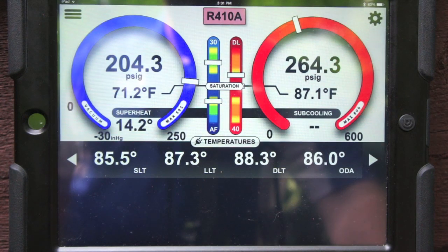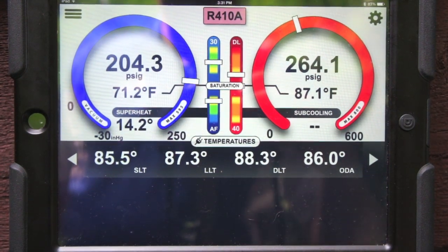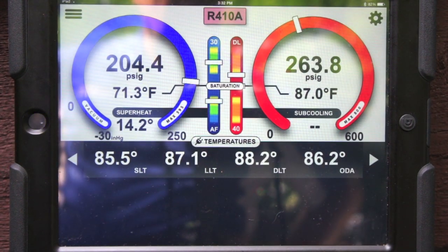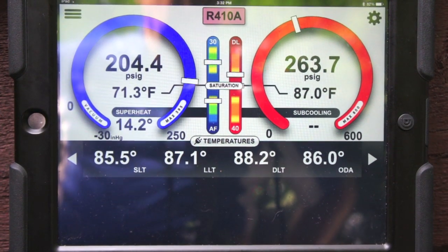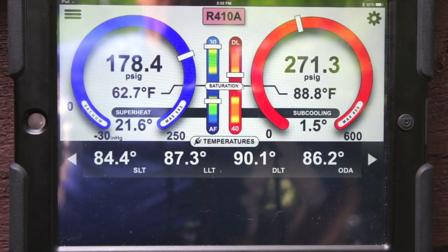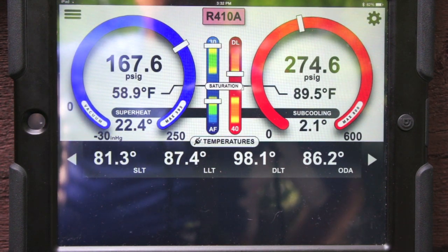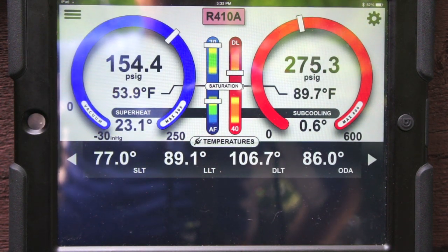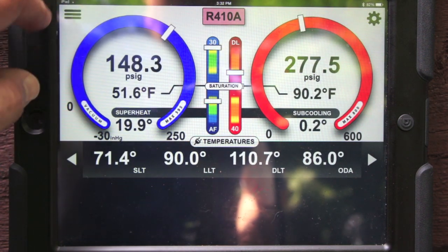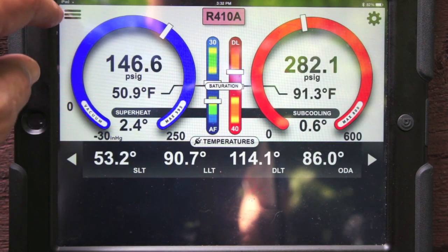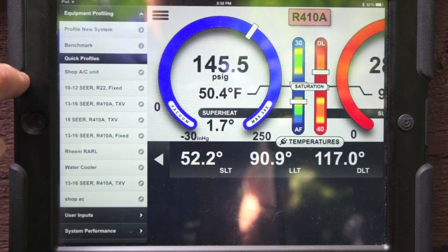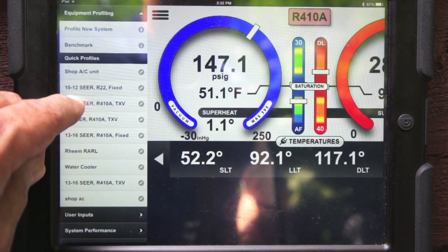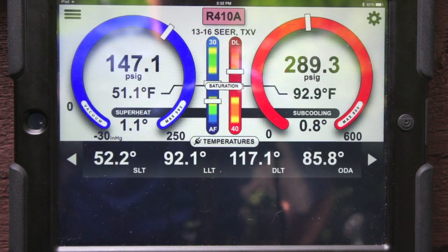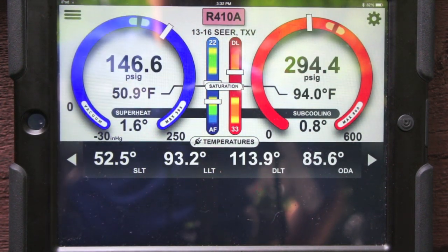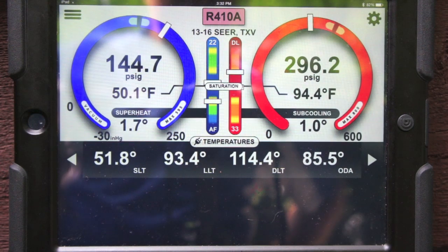We'll go to iManifold here, and we're going to go ahead and start the system up and start getting some readings. Alright, we are started up now, and you're going to start seeing some of the readings come in. So while this thing is running, I'm going to go ahead and profile the system. And this is a 13 to 16 SEER 410A TXV system. So I'm going to go ahead and select that. And that's going to put some indicators up on there showing where my pressures and my temperatures should be.